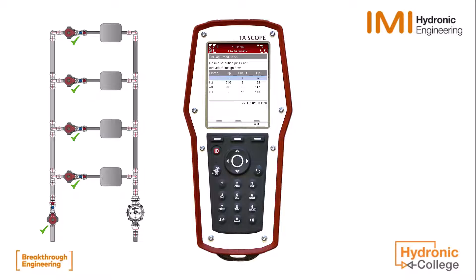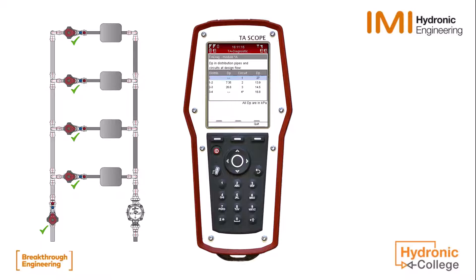Here we can see the calculated differential pressure in all areas of the module when design flow is achieved. These values can be used for diagnostics. For example, the pressure drop between circuit 2 and 3 is relatively high at 26.8 kPa, which could possibly indicate a blocked pipe or similar. If you are measuring on a project calculated in HiSelect, you will be given a warning if these figures differ from design values.